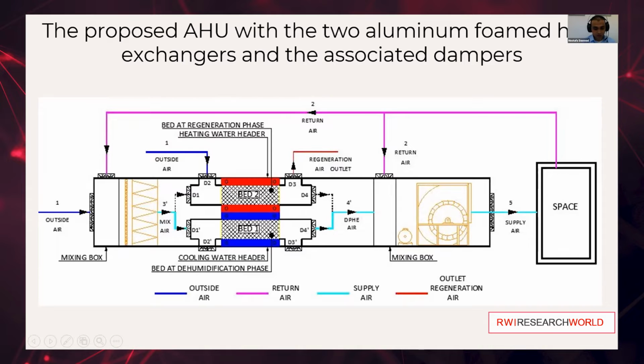The mixed air at point 3' is directed by means of control dampers to the bed which undergoes cooling and dehumidification. This bed has cooling water that flows in its channels at 20 degrees Celsius in order to cool and dehumidify the air passing through the bed to reach air conditions at point 4'. However, air at point 4' requires more cooling in order to achieve supply conditions of the room. Then it is mixed with the rest of the return air from the room in order to satisfy the supply conditions, while at the same time, the regeneration bed receives ambient air from outside and heating water at 40 degrees Celsius flows inside the water channels of this bed in order to regenerate the desiccant and remove vapor from the desiccant with the airflow.